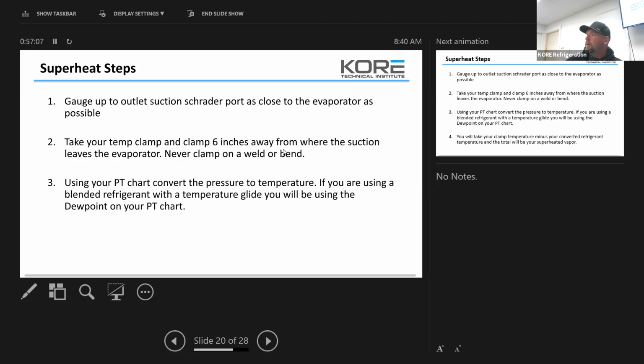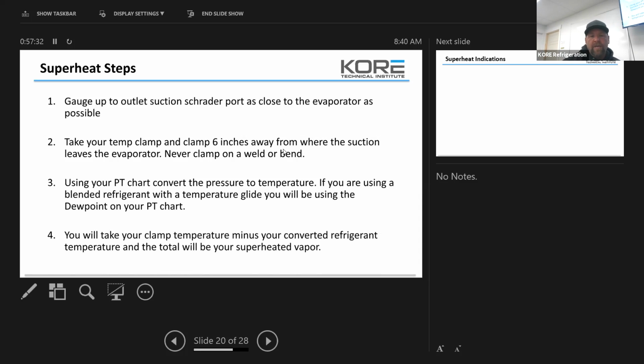Your pressure is going to be lower than your temperature. So if your pressure's at X and your temperature is 6 degrees warmer after you convert, that's superheat. You're checking the vapor; the refrigerant has boiled and it's past the point of vaporization. We're heating it past its boiling point. It's picking up more heat after it's boiled off to a vapor. That's what superheat is. You take your clamp temperature minus your converted refrigerant temperature, and the total will be your superheat.